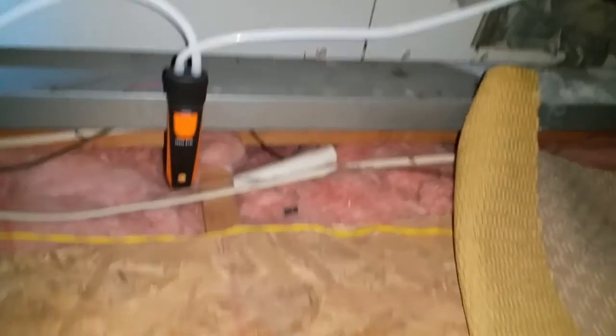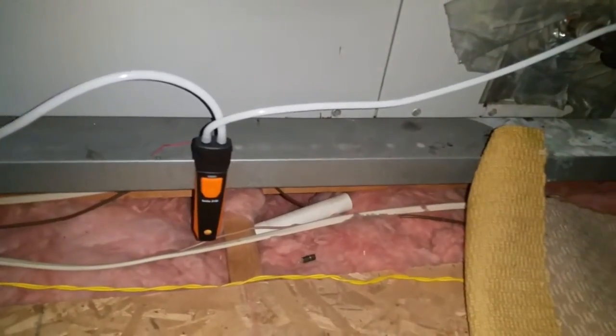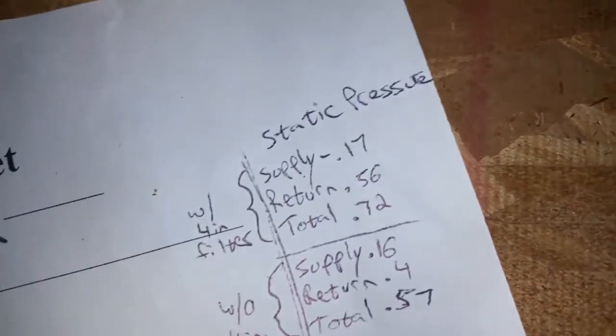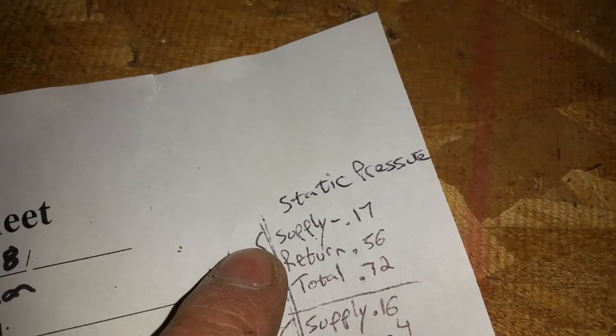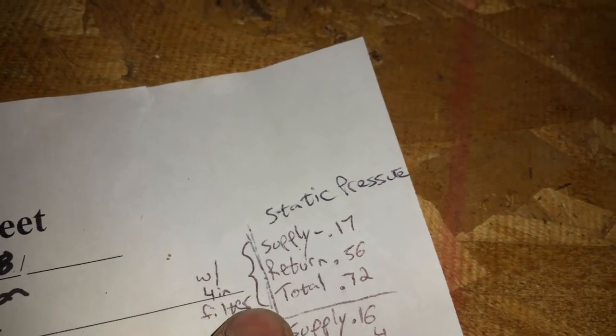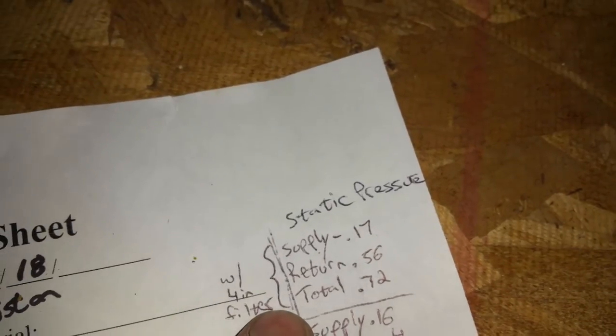Not bad at all. Let me show you what I've got. I've got one probe in the return and another in the supply. My static pressures are as follows: with the 4-inch filter in, my supply is reading 0.17, my return is 0.56, and total static is 0.72.